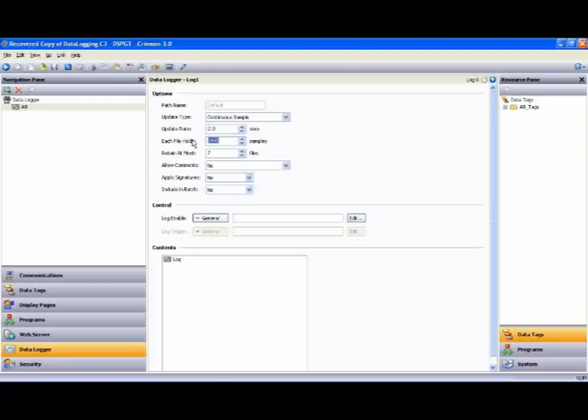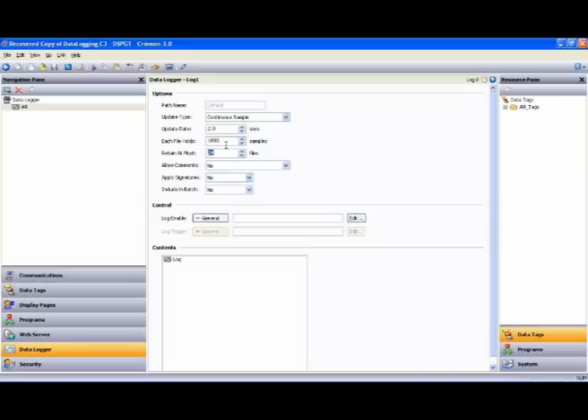How many samples in each file? Make that 1,800. And how many files do we want to create? Make that 24. So, what we just did in this example is set the Data Logger up to log 24 hours of data, with each file representing one hour of samples.